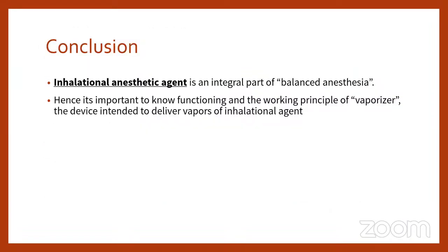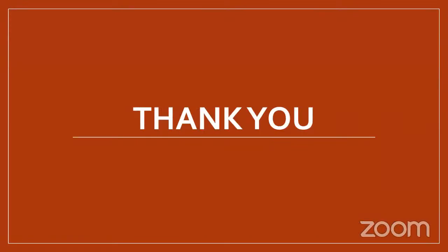Conclusion: inhalation anesthetic agent is an integral part of balanced anesthesia. Hence, it's very, very important to know the functioning and working principles of all vaporizers, at least the vaporizers that we are using in our day-to-day practice. The vaporizer is a device intended to deliver vapors of inhalation agent to the patient. It is the anesthetist who is responsible for all these things, so we must be aware of the basic principles of the vaporizer that we are using in our daily practice. Thank you so much for your patient listening.